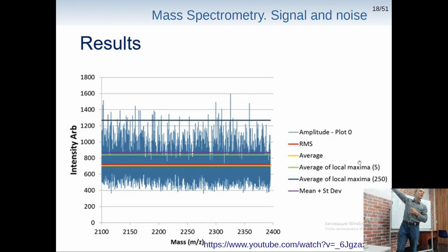Each software for each mass spectrometer will get you a little bit different results. So that's just a problem. Actually, there would be a lot of things that would be non-standardized. For instance, resolution can be as a resolution itself or as a resolving power. And those two are used interchangeably, but they have a little bit different formula to calculate. Just one example.